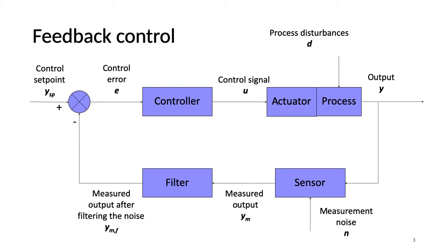The controller gives a control signal U to the actuator, connected to the process, in order to manipulate the process. The output variable Y is the variable that needs to be controlled. Process disturbances are non-controlled input variables acting on the process and influence its output. The measured output is the output from the sensor after measuring the process variable, and it contains measurement noise. The filter smooths out this random noise; otherwise noise can propagate to the control signal causing unnecessary process fluctuations.